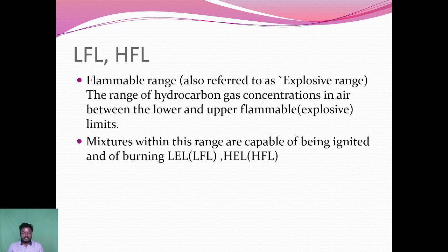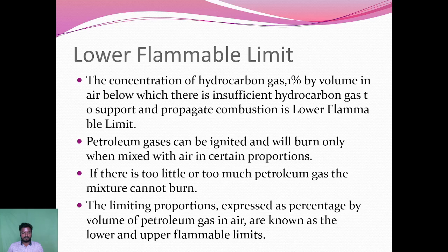Mixtures within the range are capable of being ignited or burned; the limits are the LFL and UFL. First we are going to see the lower flammability limit. It is the concentration of hydrocarbon gas of 1% by volume of air below which there is insufficient hydrocarbon gas to support and propagate combustion.